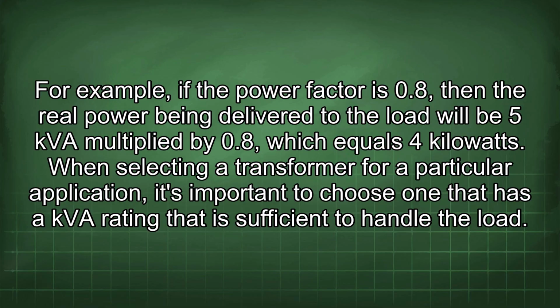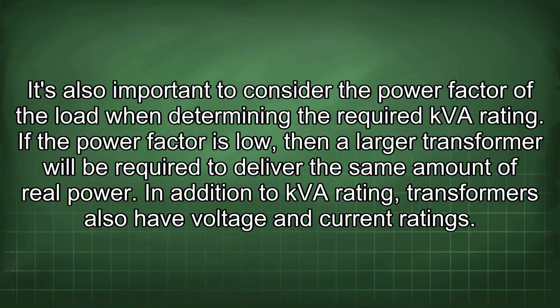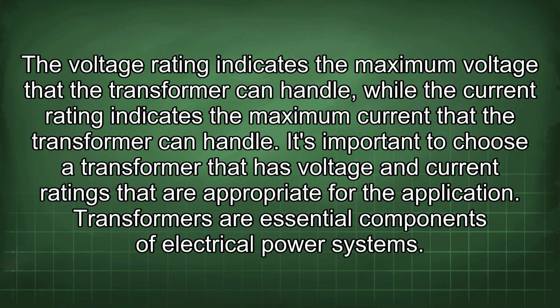When selecting a transformer for a particular application, it's important to choose one that has a kVA rating that is sufficient to handle the load. It's also important to consider the power factor of the load when determining the required kVA rating. If the power factor is low, then a larger transformer will be required to deliver the same amount of real power. In addition to kVA rating, transformers also have voltage and current ratings. The voltage rating indicates the maximum voltage that the transformer can handle, while the current rating indicates the maximum current that the transformer can handle. It's important to choose a transformer that has voltage and current ratings that are appropriate for the application.